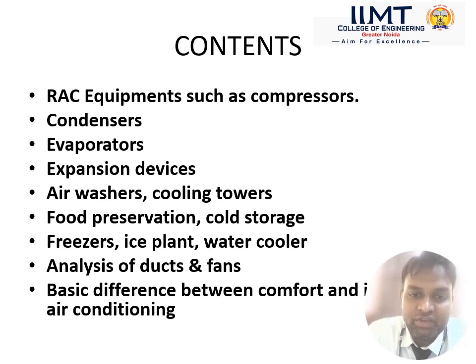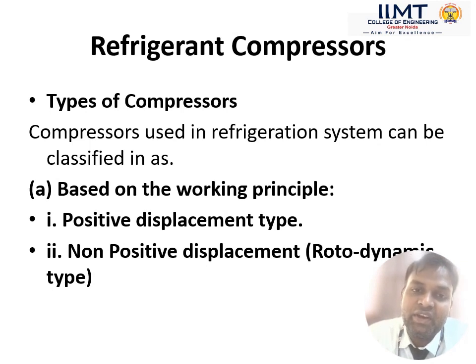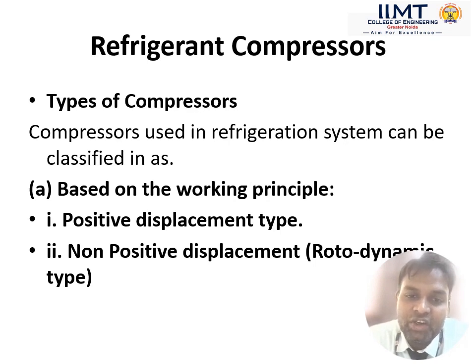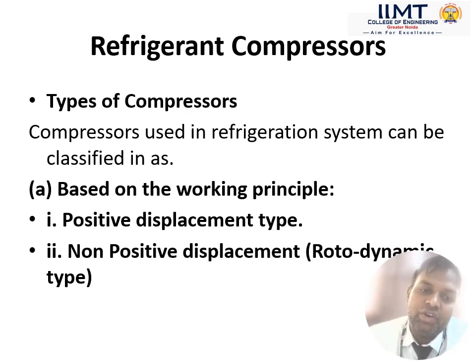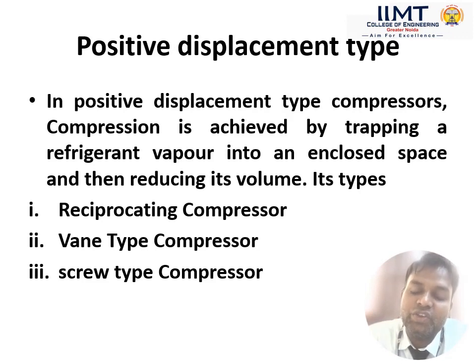Regarding the refrigerant compressor used in refrigeration and air conditioning industries, there are basically two types classified based on working principle. The first is positive displacement type and the second is non-positive displacement type. In positive displacement type, compression is achieved by trapping refrigerant gas into an enclosed space and then reducing its volume.